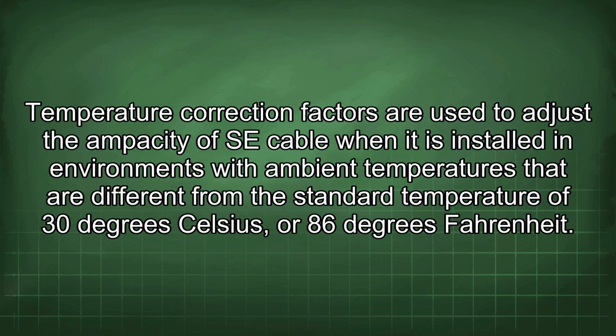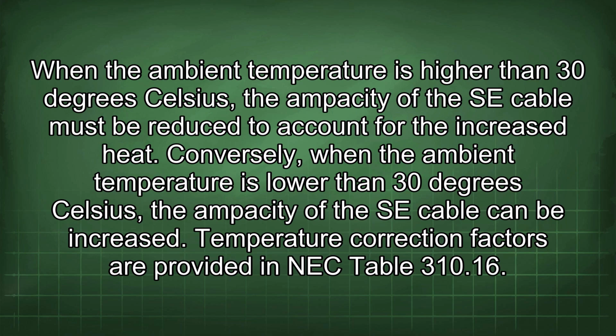Temperature correction factors are used to adjust the ampacity of SE cable when it is installed in environments with ambient temperatures that are different from the standard temperature of 30 degrees Celsius or 86 degrees Fahrenheit. When the ambient temperature is higher than 30 degrees Celsius, the ampacity of the SE cable must be reduced to account for the increased heat. Conversely, when the ambient temperature is lower than 30 degrees Celsius, the ampacity of the SE cable can be increased. Temperature correction factors are provided in NEC Table 310.16.